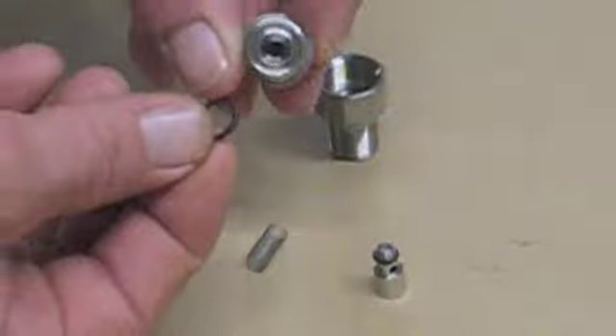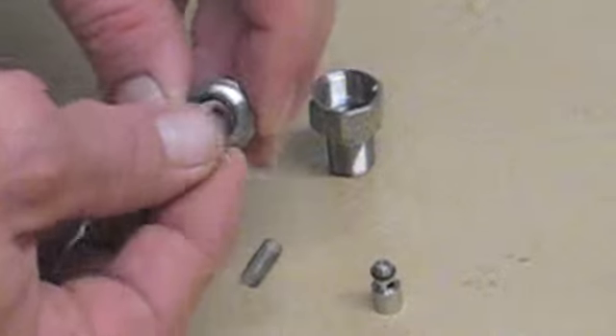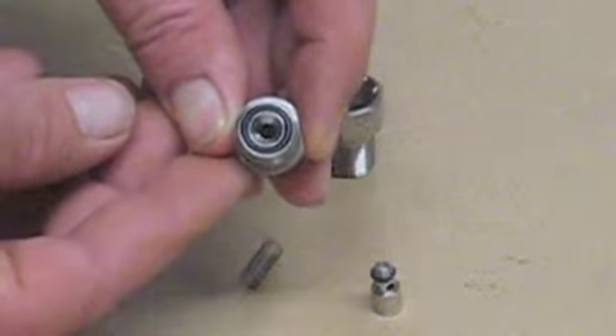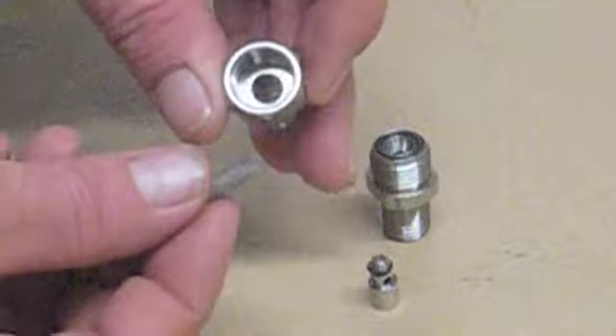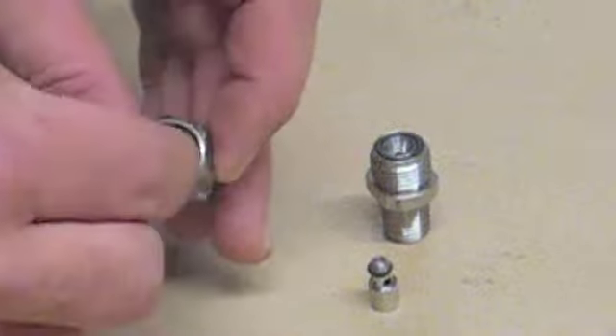This is a face seal for the seat. Make sure it is down and remains in place. Put the one PSI spring down here. Put the poppet on top of the spring, making sure it is seated well.